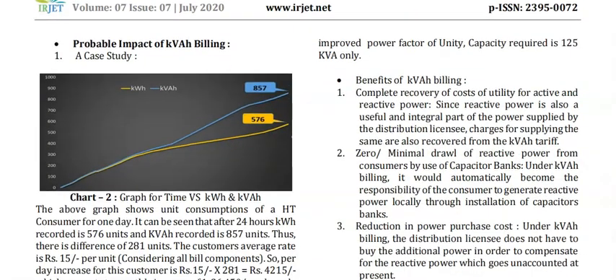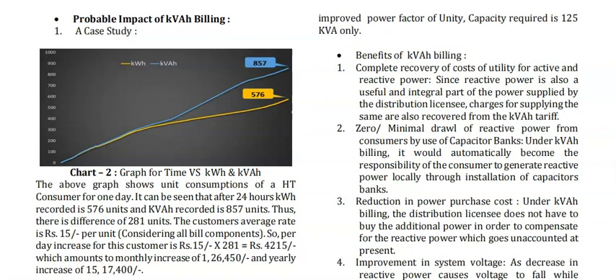Let us see a case study. This graph shows time versus kilowatt hour and kVAh. This one is kilowatt hour and this is kVAh. We are using a billing system. The graph shows the unit consumption of an HT consumer for 1 day. After 24 hours, kilowatt hour recorded 576 units and kVAh recorded 857 units. There is a difference of 281 units, and the customer average rate is 15 per unit, considering all bill components.